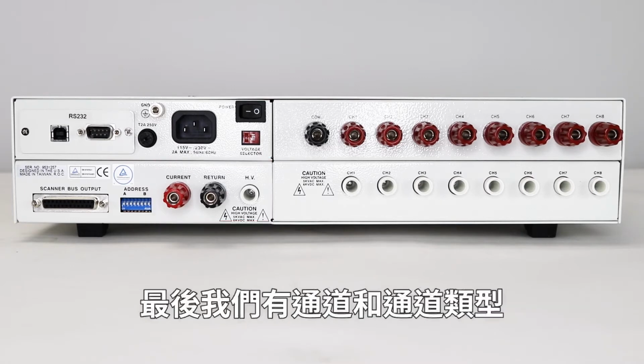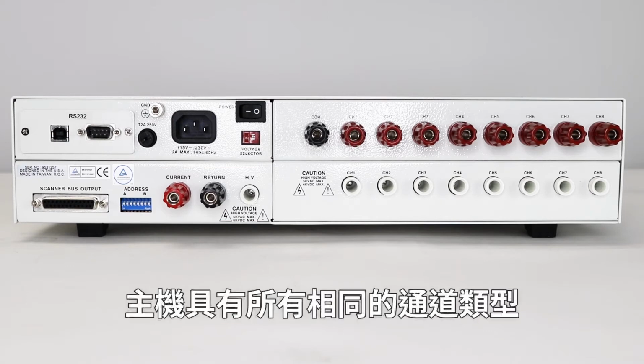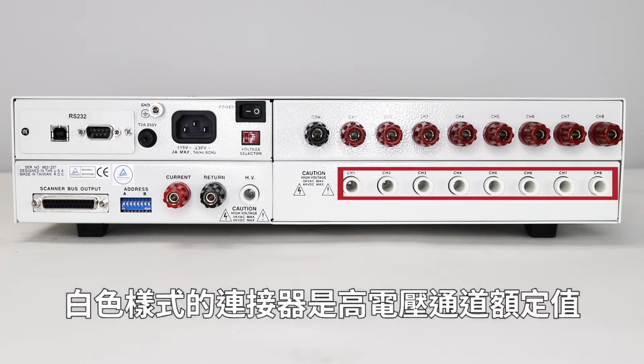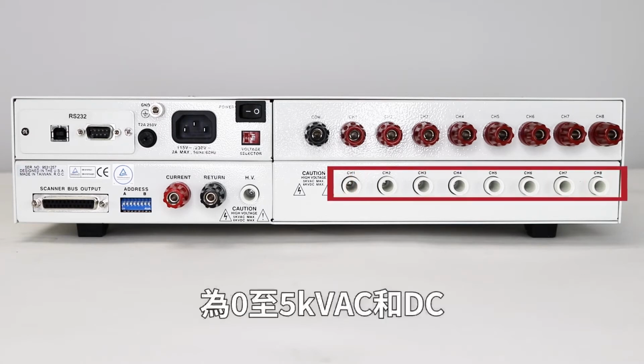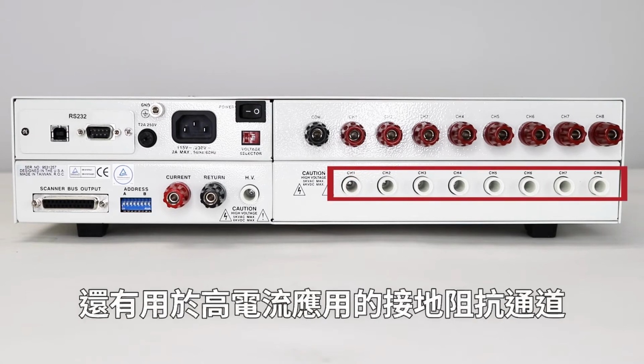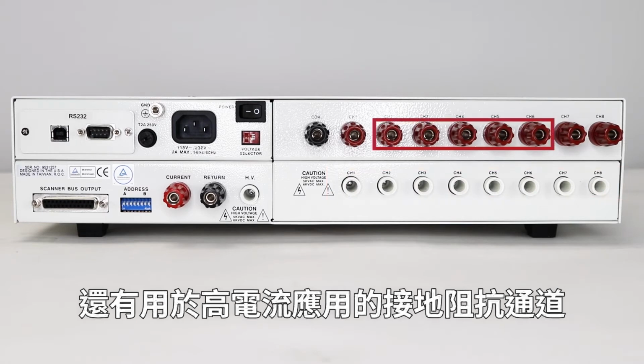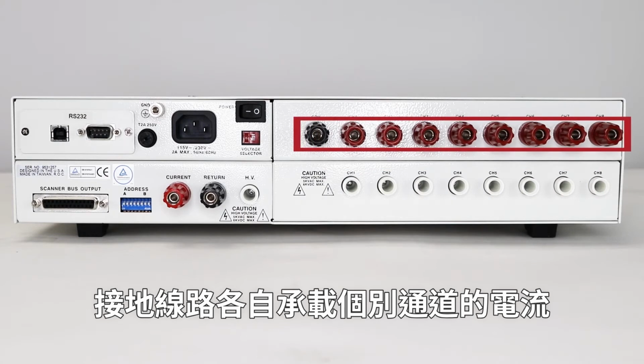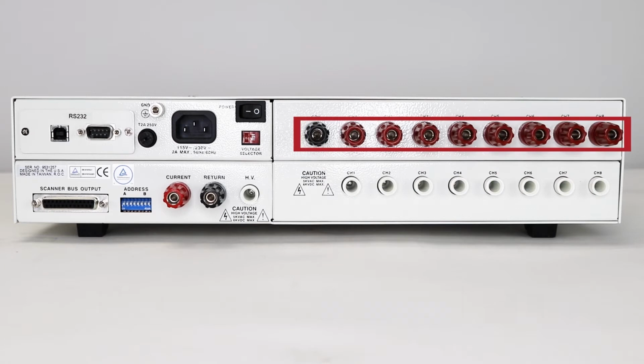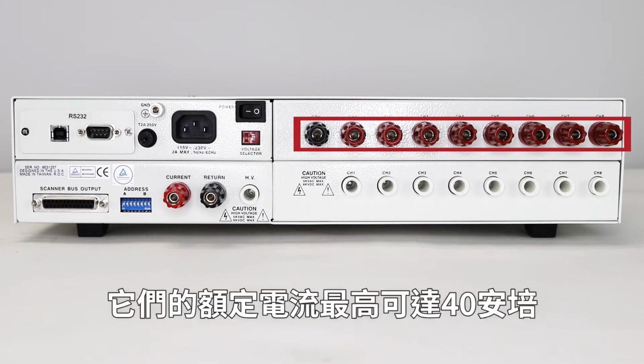Finally, we have the channels and the channel types. The main has all the same channel types. The white style connectors are high voltage channels, rated from 0 to 5 kV AC and DC. There are also ground bond channels for high current applications. The ground bond channels run individual current from an individual channel back to the GCOM port. They're rated for up to 40 amps.